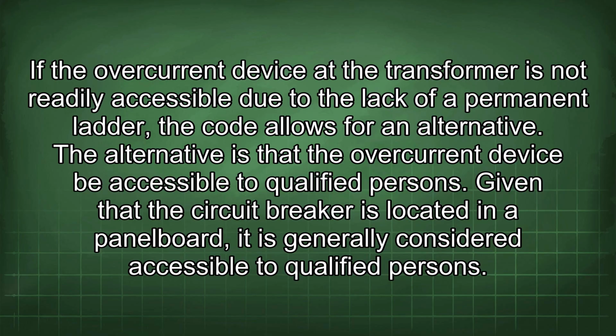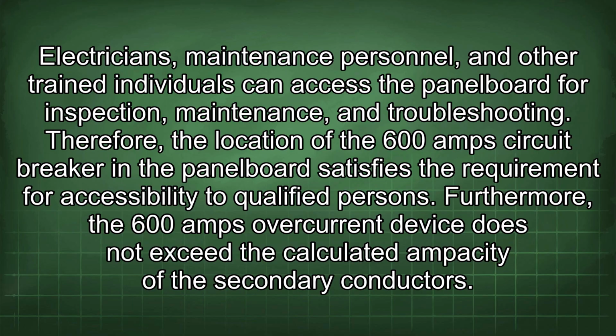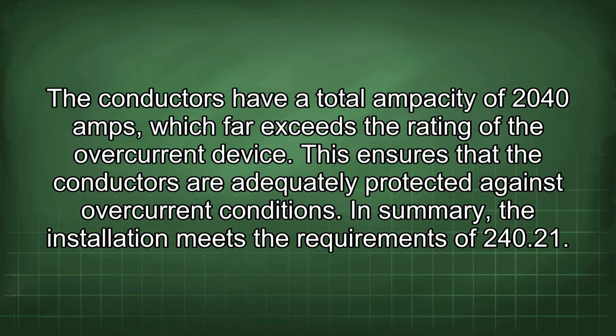Given that the circuit breaker is located in a panel board, it is generally considered accessible to qualified persons. Electricians, maintenance personnel, and other trained individuals can access the panel board for inspection, maintenance, and troubleshooting. Therefore, the location of the 600 amp circuit breaker in the panel board satisfies the requirement for accessibility to qualified persons. Furthermore, the 600 amp overcurrent device does not exceed the calculated ampacity of the secondary conductors. The conductors have a total ampacity of 2040 amps, which far exceeds the rating of the overcurrent device. This ensures that the conductors are adequately protected against overcurrent conditions.